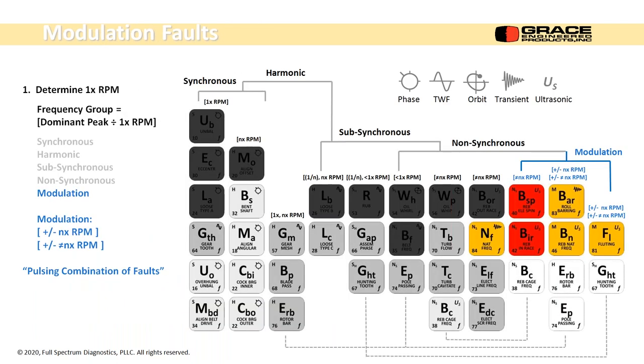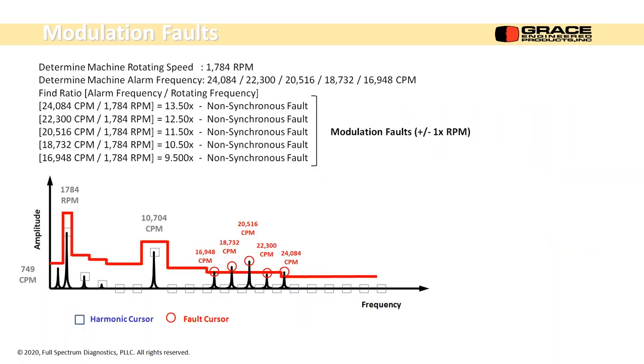The last grouping is modulation. A lot of times you can hear it. It's a pulsating combination of faults. Listening to it, you can hear the pulsing sometimes. Measuring it in the time waveform, a lot of times it's a lobing beat frequency that you'll see. But in the spectrum, it's something a little bit different. It has what's called sidebands. So the only way to show you this is to show you by example.